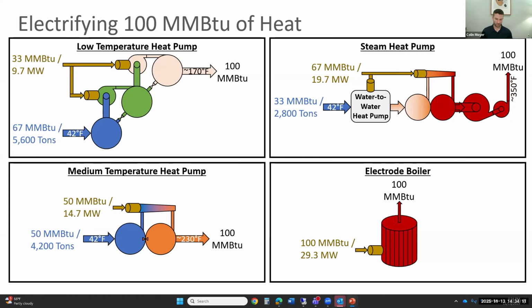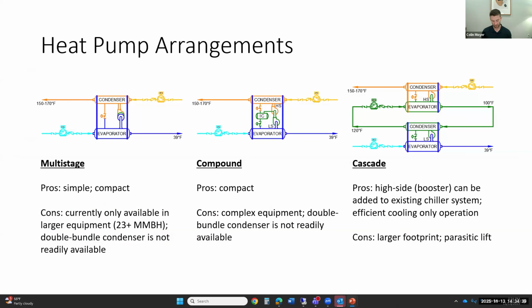So this is just some background in terms of why UC Davis already embarked on a campus-wide steam to hot water conversion. That 350-degree steam system is in the process of being converted to a 170-degree low-temperature hot water system, possibly could operate even a little bit lower than that. And so that's going to improve the efficiency. The amount of work required is going to be cut in half from 67 to 33 for the heat pump system. And so recently, UC Davis has been looking at proposals from different design build providers on the low temperature heat pump system. And it came down to a very close analysis of 3 different types of machines.